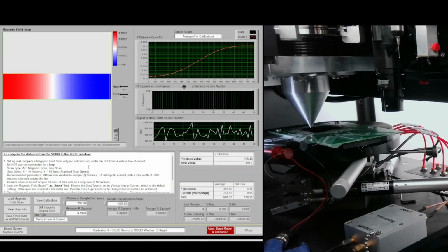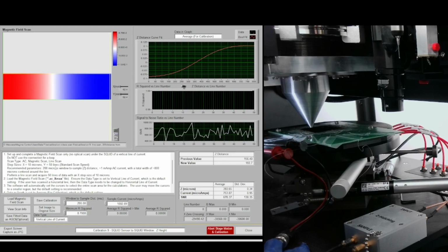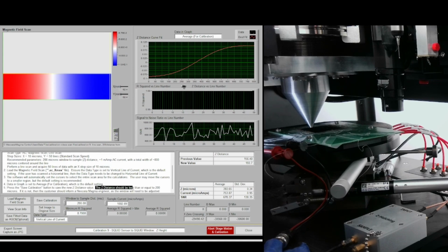If the value exceeds 200, say 201, that means the SQUID window is too far, and a manual adjustment will be needed. In that case, we stop here and contact the team. If the Z distance is within spec, we click Save Calibration, and just like that, Calibration 9 is complete.